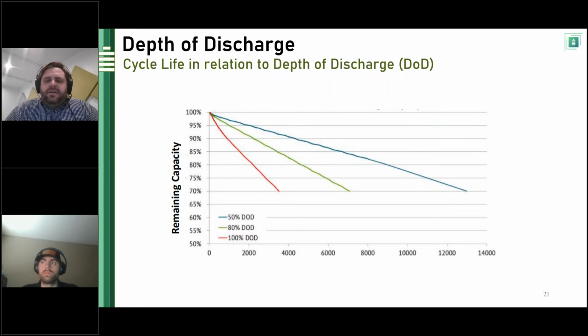But as far as daily cycling of the battery goes, no matter what the cycle warranty or the specification of the battery is, a shallower depth of discharge will give you more cycles and a longer life than a deeper depth of discharge. We feel the appropriate compromise in your daily cycling, because again, you're buying the batteries for some economic motivation and some backup motivation. So what's the right balance between fully discharging your battery and gaining the economics, or retaining some reserve capacity and being prepared for power outages at all times of day? To some extent, those are contradictory messages.